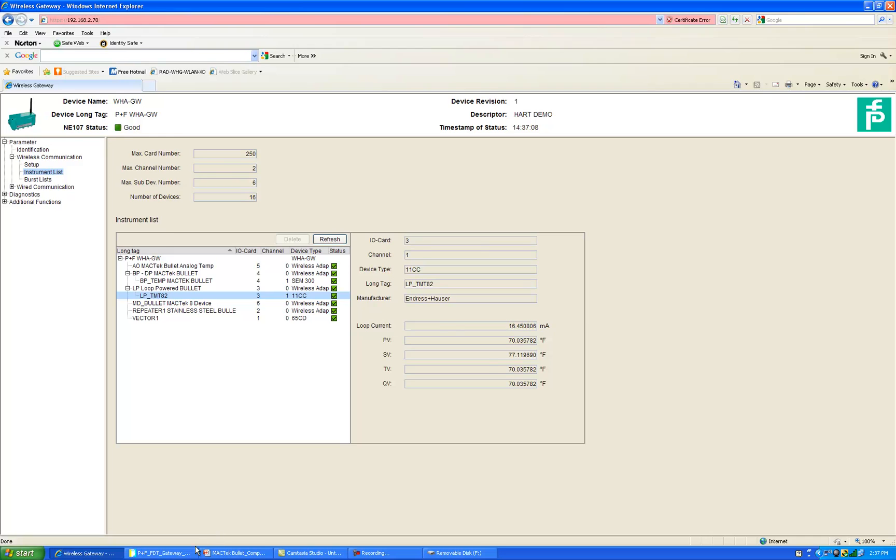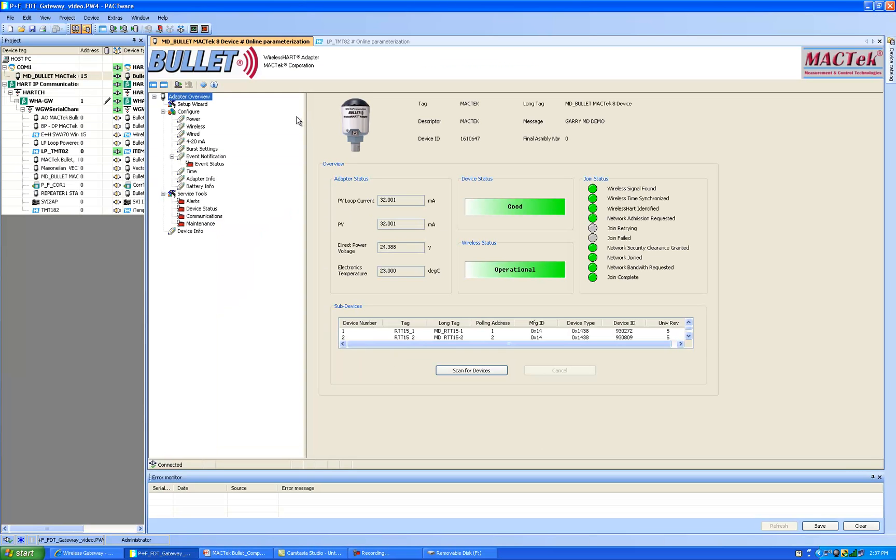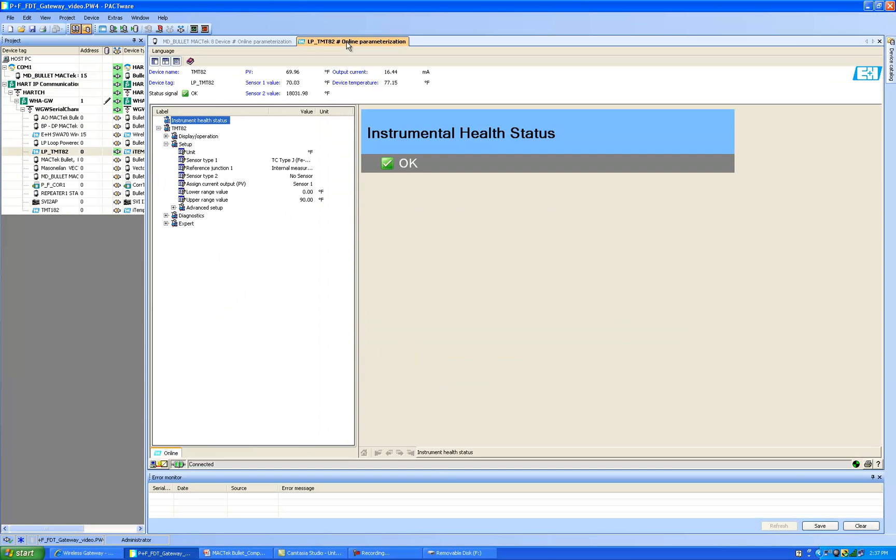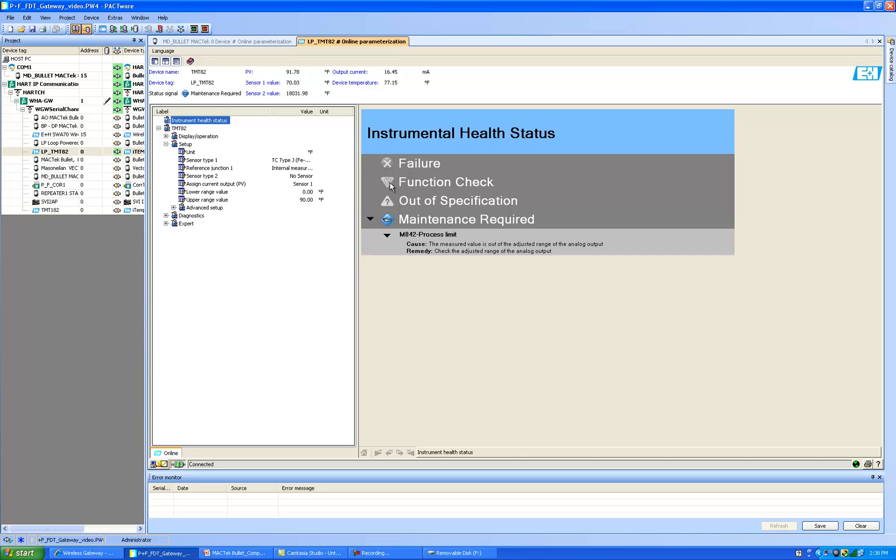So back at our DTM, our Pactware screen, I'm going to click on the DTM for the Endress Hauser TMT-82 and this device has a nice overview page where it gives you a nice indication of instrument health. What I'm going to do just temporarily is I'm going to hold on to the thermocouple and see what status change we get. Now you can see the status has changed and they give you a nice clear indication that the health status is out of specification maintenance required.